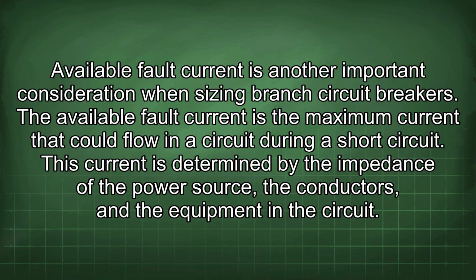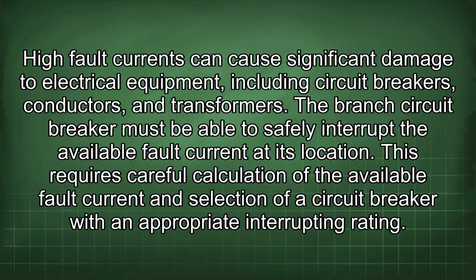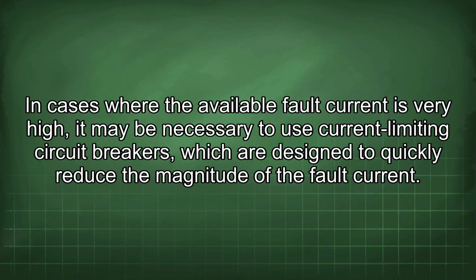Available fault current is another important consideration when sizing branch circuit breakers. The available fault current is the maximum current that could flow in a circuit during a short circuit. This current is determined by the impedance of the power source, the conductors, and the equipment in the circuit. High fault currents can cause significant damage to electrical equipment, including circuit breakers, conductors, and transformers. The branch circuit breaker must be able to safely interrupt the available fault current at its location. This requires careful calculation of the available fault current and selection of a circuit breaker with an appropriate interrupting rating. In cases where the available fault current is very high, it may be necessary to use current-limiting circuit breakers, which are designed to quickly reduce the magnitude of the fault current.